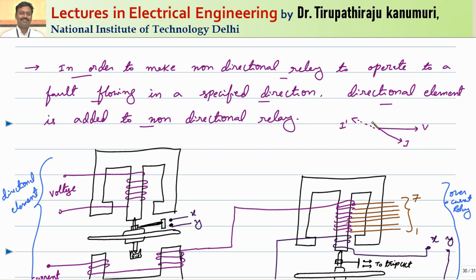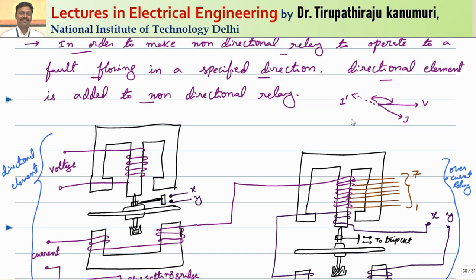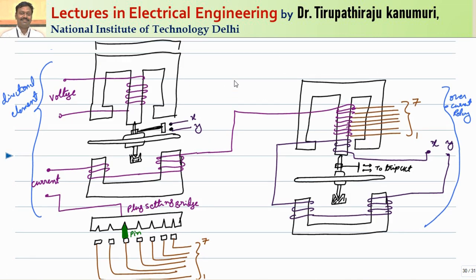When the direction of current is reversed, the current is now leading the voltage. The torque is produced due to the interaction of two fluxes, and the torque is produced in the direction from the leading flux to the lagging direction — as we have already seen in previous lectures with the induction disk. That is why the direction of torque will be reversed, and because of that the relay will operate. The directional element has an upper magnet and a lower magnet; the upper magnet winding is connected to the supply voltage through a potential transformer.